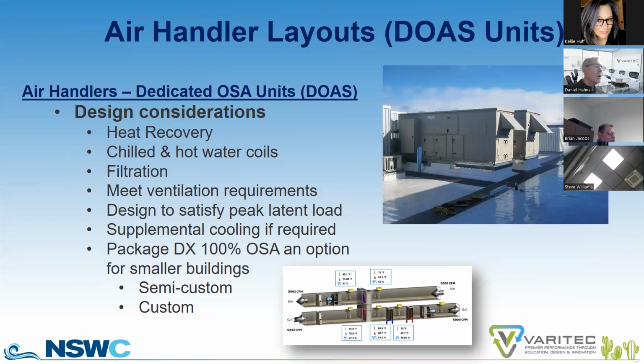We can put chilled or hot water coils. We've found a very compelling technology is what can be done now with DX 100% outside air units through our manufacturers, using variable speed compressors for tight control of air conditions, dehumidification, and leaving air conditions. We want to make sure the unit is properly filtered, but if you provide a 100% outside air unit, it does beg the question, do you need MERV 13 filtration and the inherent static pressure penalty paid on fan energy for that enhanced filtration? Well, you have no return air back to a building, so the answer is no. You want to design the DOAS to meet as a minimum the ventilation requirements for that building as defined by 62.1. But remember, 62.1 provides minimum outside air requirements, not necessarily best outside air requirements to enhance building IAQ.